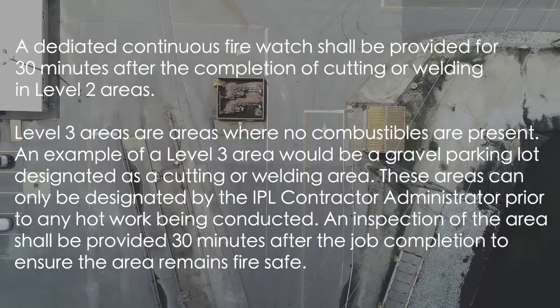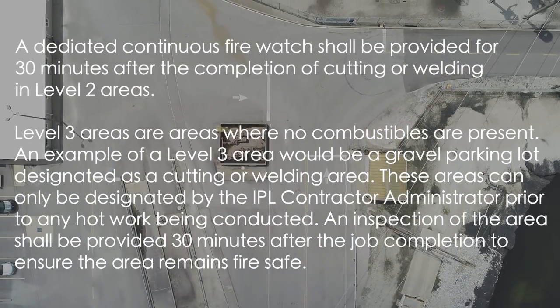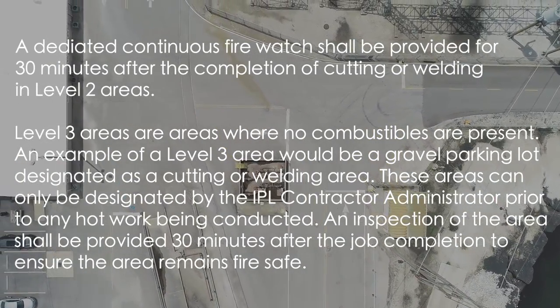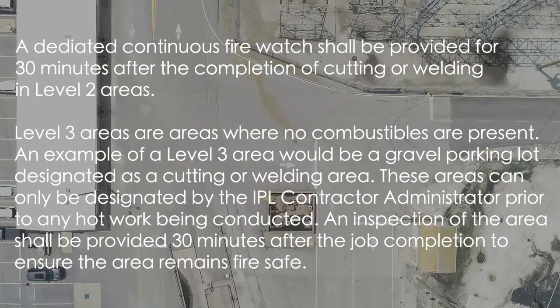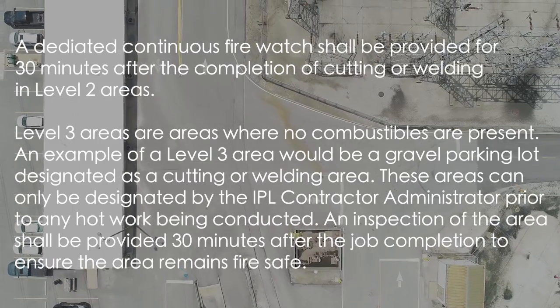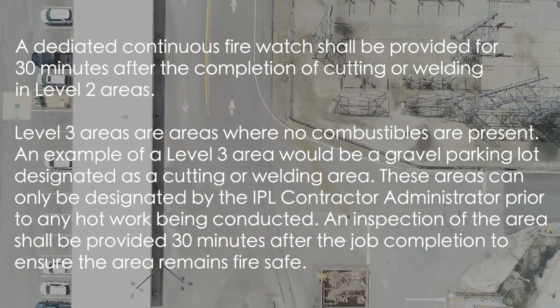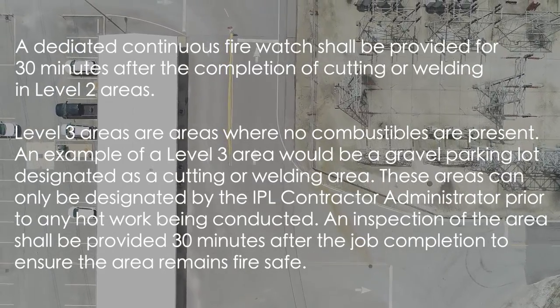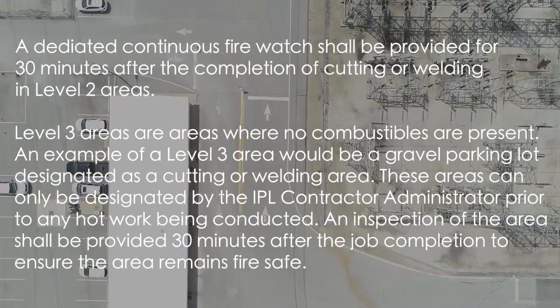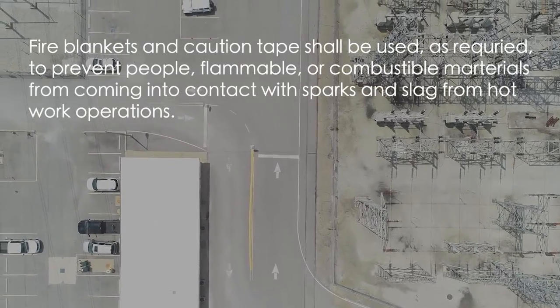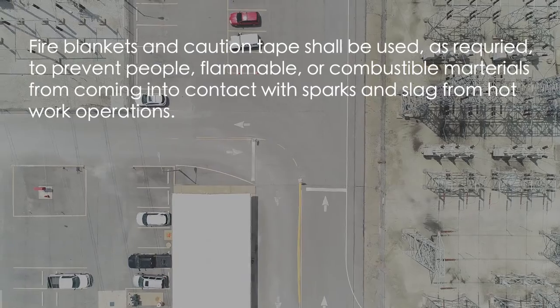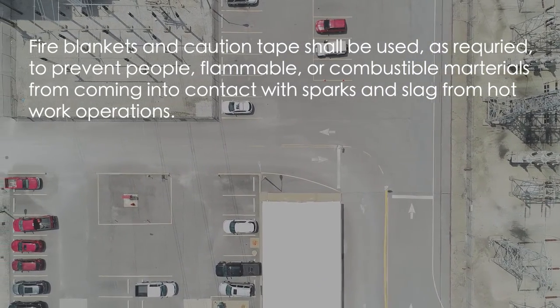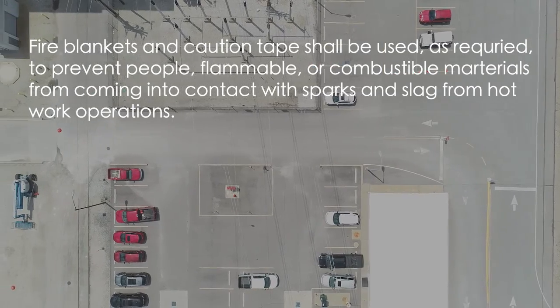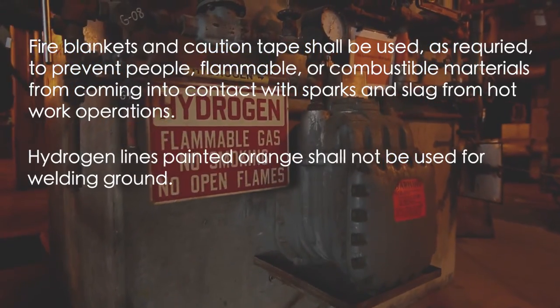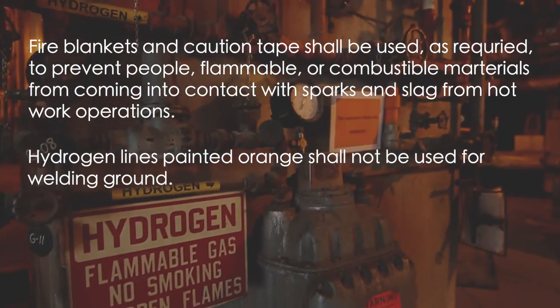Level 3 areas are areas where no combustibles are present. An example of a Level 3 area would be a gravel parking lot designated as a cutting or welding area. These areas can only be designated by an IPL contractor administrator prior to any hot work being conducted. An inspection of the area shall be provided 30 minutes after the job completion to ensure the area remains safe. Fire blankets and caution tape shall be used as required to prevent people, flammable or combustible materials from coming into contact with sparks or slag from hot work operations. Hydrogen lines, painted orange, shall not be used for welding ground.